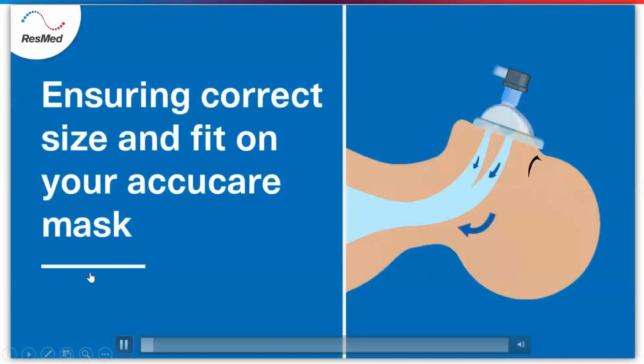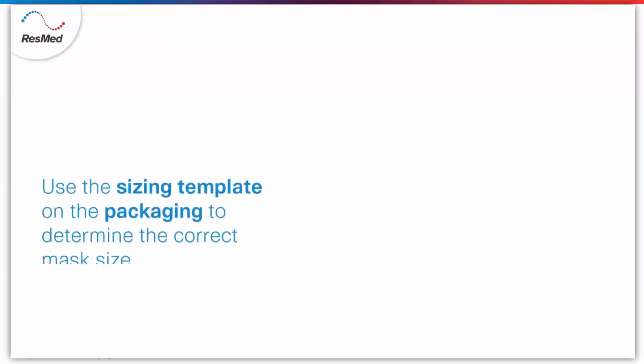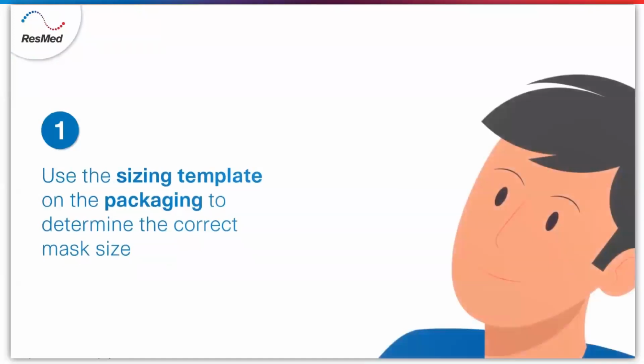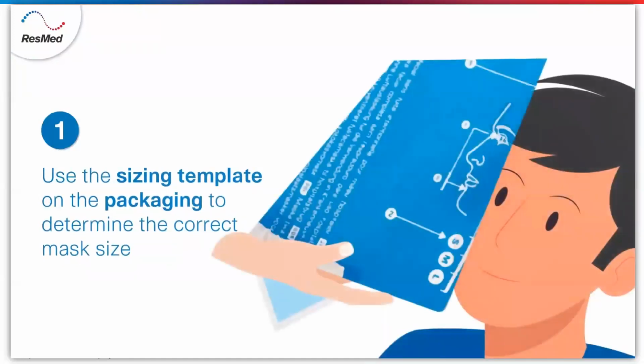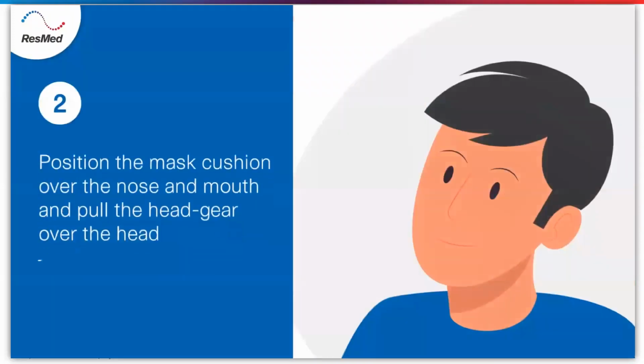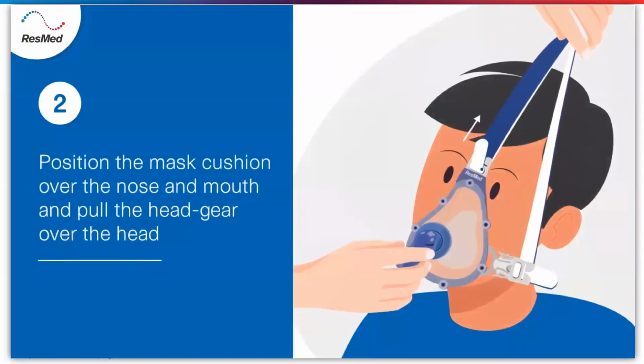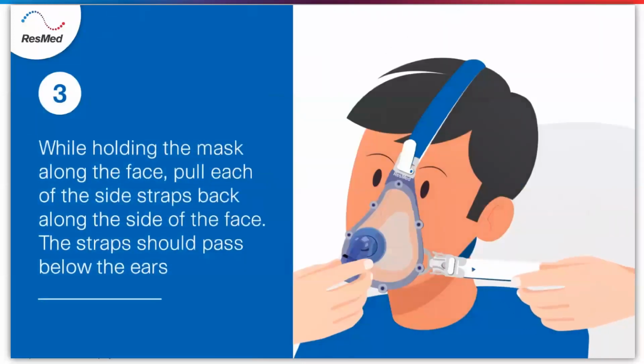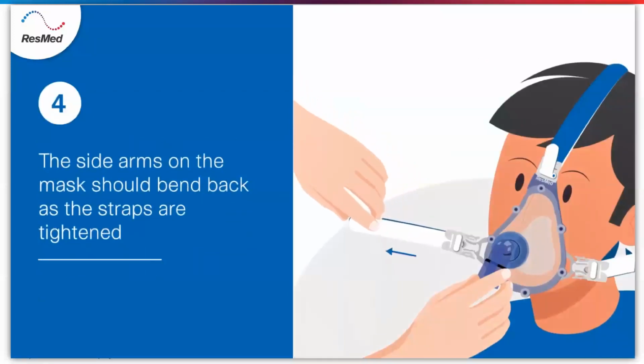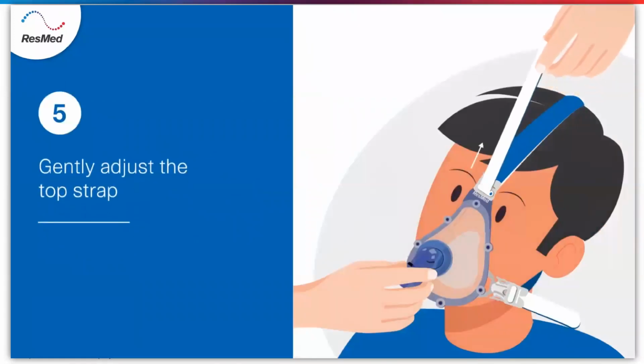Follow these instructions to ensure the correct fit of the AccuCare mask on your patient's face. Use the sizing template on the packaging to determine the correct mask size. Position the mask cushion over the nose and mouth and pull the headgear over the head. While holding the mask along the face, pull each of the side straps back along the side of the face. The straps should pass below the ears. The side arms on the mask should bend back as the straps are tightened. Gently adjust the top strap.